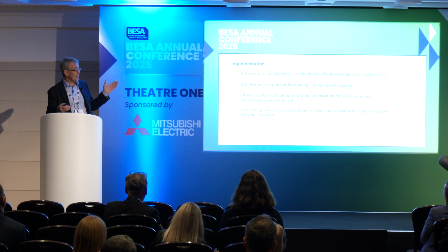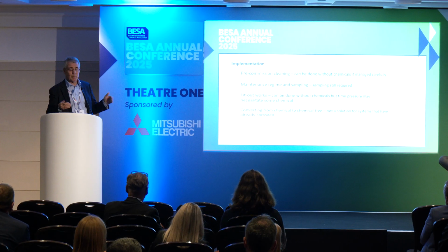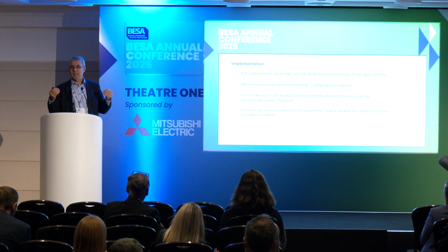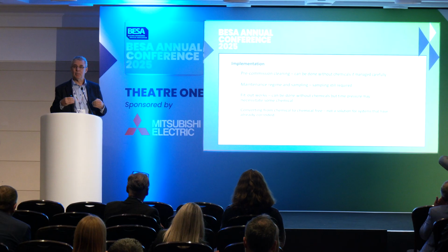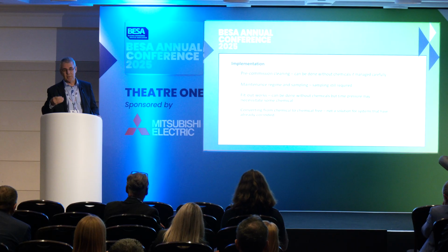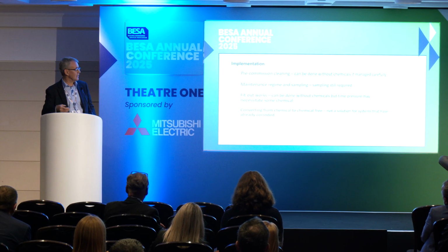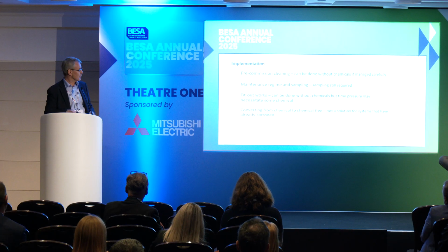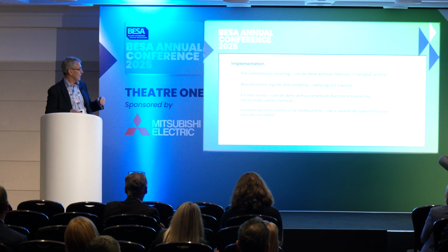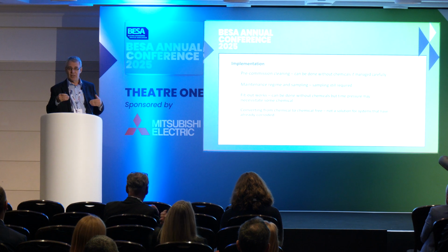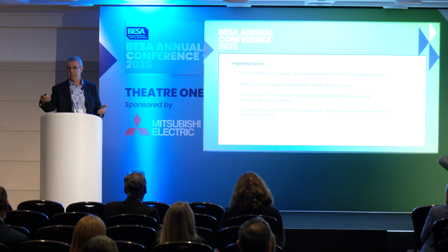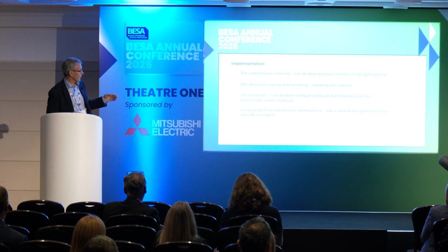Now, generally speaking, these things are manageable. For pre-com cleaning, you need to know you've got a fairly clean system to begin with, because you can do chemical-free cleaning, but not in a system that's already badly corroded or full of biofilm. So there needs to be a little bit of awareness on behalf of the contractor and the cleaning specialist to understand just what the state of the system is. You still need to sample and check that you're maintaining pH levels and bacteria levels and other key parameters, but probably no need for such frequent monitoring.